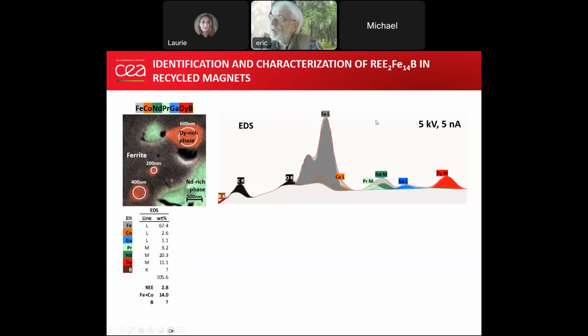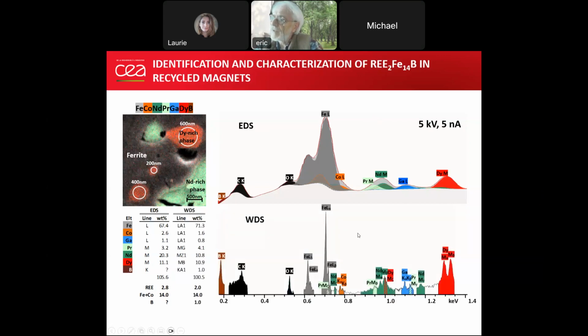And so the solution is to rely on the WDS, because with the WDS we can separate all X-rays, as shown here. Dysprosium, here we can see the M-alpha and beta, but we can separate all X-rays and choose which one we want to use to make the quantification. It's not necessary to measure all X-ray lines, of course. We just have to measure the maximum of each X-ray line.